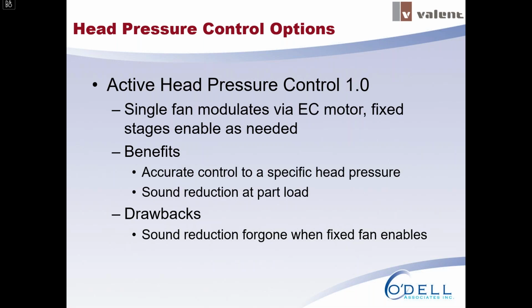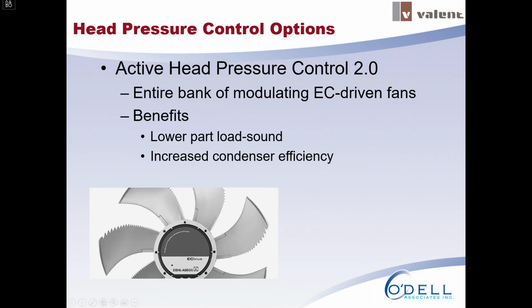The next step up, which we call head pressure control 1.0, is where your lead fan, or just one fan, will modulate with an EC motor, and then any additional condenser fans will be on or off. The benefit is you have better head pressure control. You're able to modulate one of those fans up and down. So you're going to have quieter sound at part load because you're able to modulate one fan. However, if you're at a high enough capacity where you need to turn on a second fan, now your sound jumps up because one of your fans is at full speed. So this is better, but not quite as good as our version 2.0.